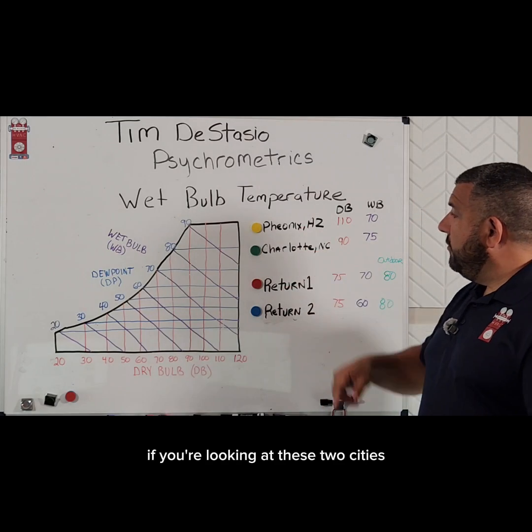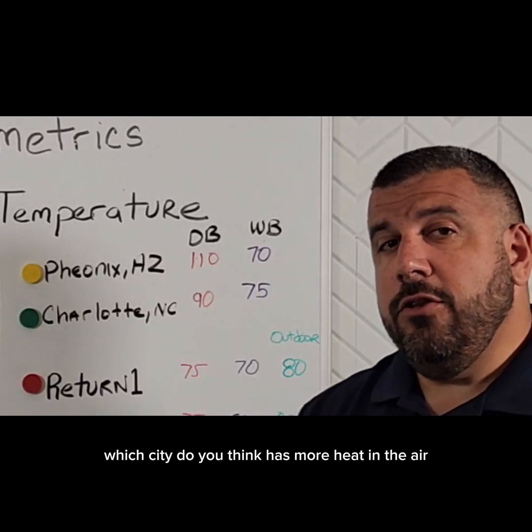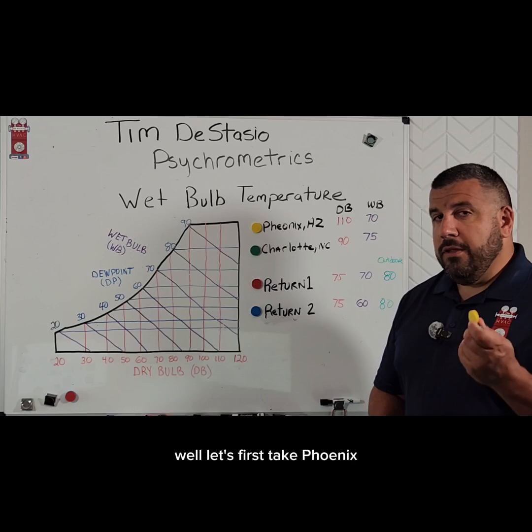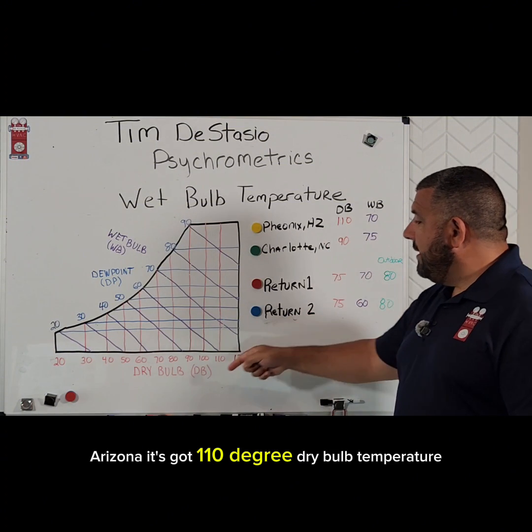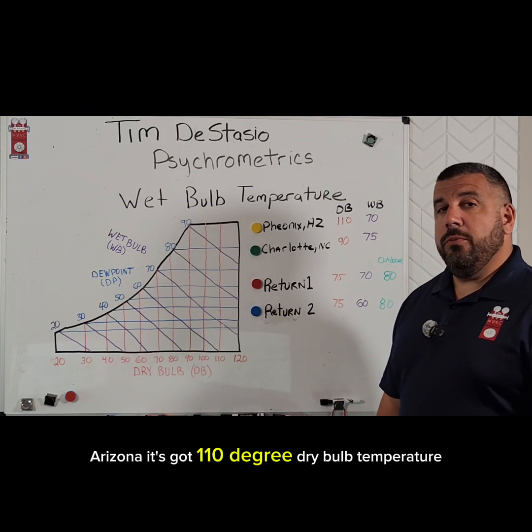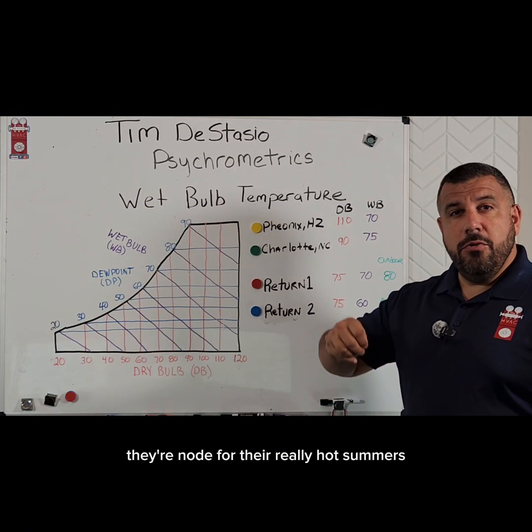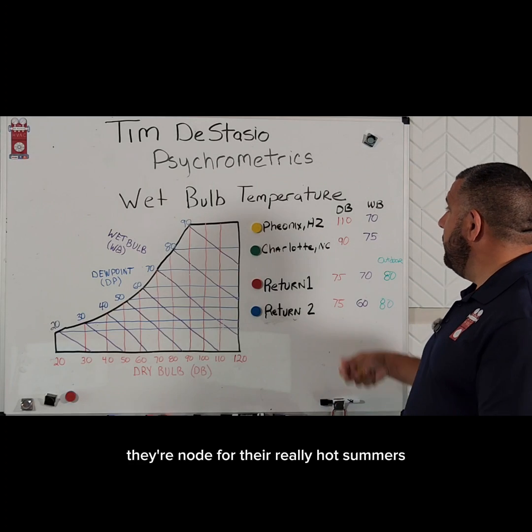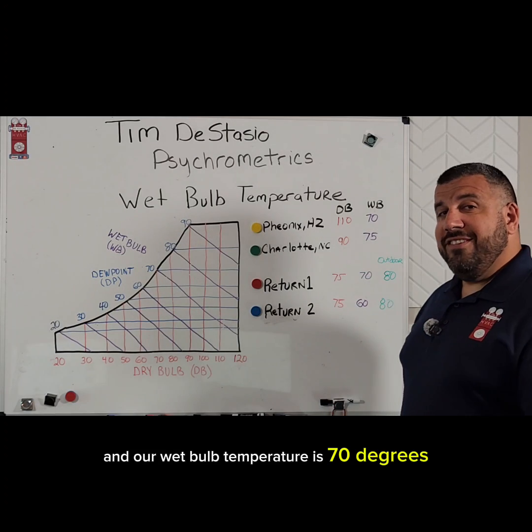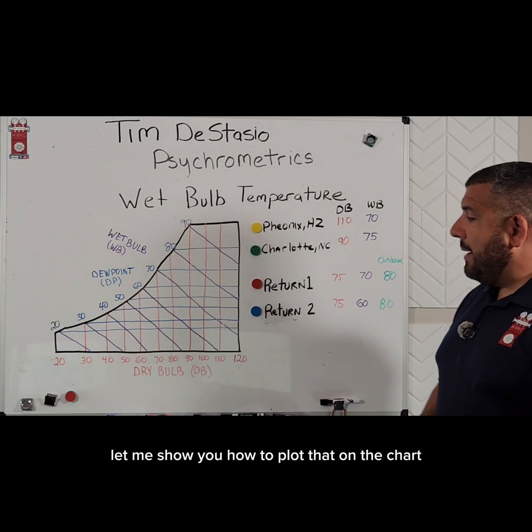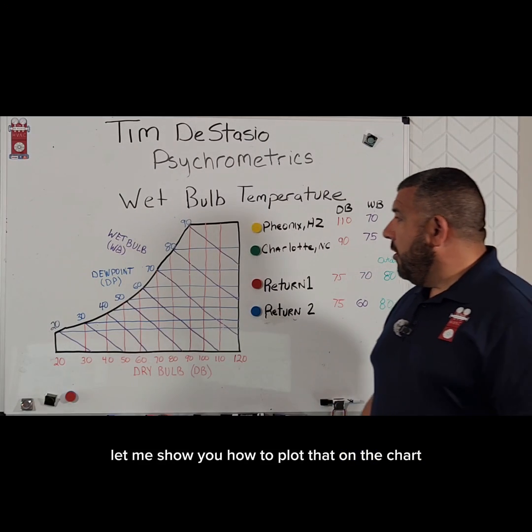If you're looking at these two cities, which city do you think has more heat in the air? Well, let's first take Phoenix, Arizona. It's got a 110-degree dry bulb temperature — they're known for their really hot summers — and our wet bulb temperature is 70 degrees. Let me show you how to plot that on the chart.